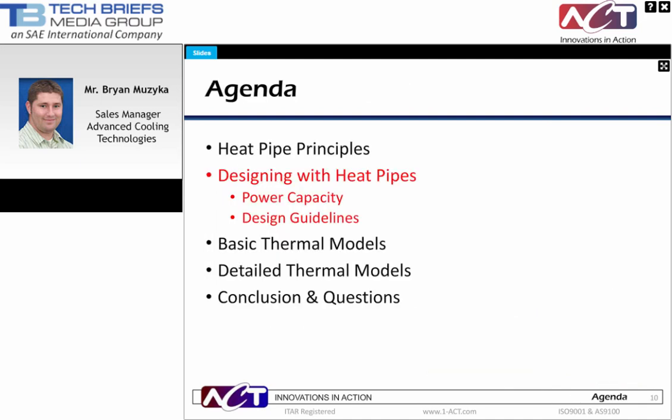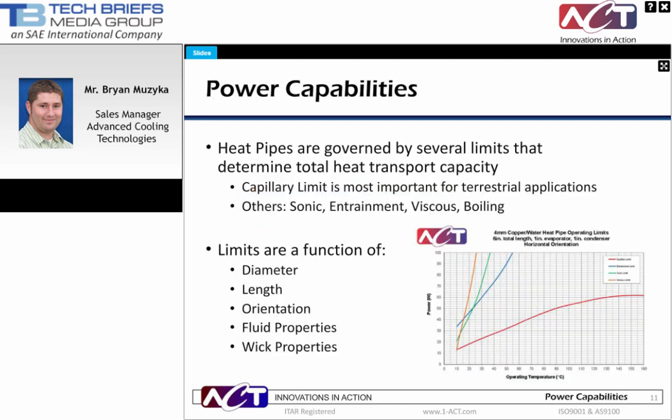Next, we'll talk about designing with heat pipes — determining power capacity and providing guidelines to help you integrate heat pipes into your system. Heat pipes are governed by several limits. For terrestrial applications, the first limit reached in most cases is the capillary limit, which is the ability of the wick structure to overcome the various internal pressure drops created in the heat pipe. Other limits include the sonic, viscous, and boiling limits. The figure shown here is a plot for all the various limits, and as you can see, the capillary limit determines the capacity in this case. The limits are a function of diameter, length, orientation, fluid properties, and wick properties.